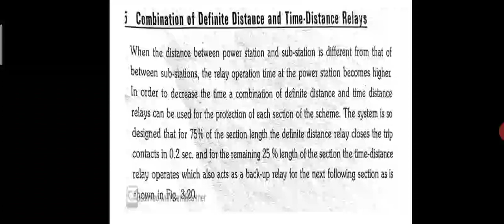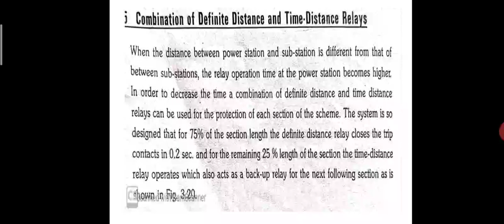So see the diagram. On the x-axis and y-axis, the y-axis takes power station, substation A, substation B, substation C, and these are the times 0.2, 0.4, 0.6, 0.8, 1.0, 1.2, 1.4. The relay closes the trip contact in 0.2 seconds. For the remaining 25% of the length of the section the time distance relay operates, which also acts as a backup relay for the next section.